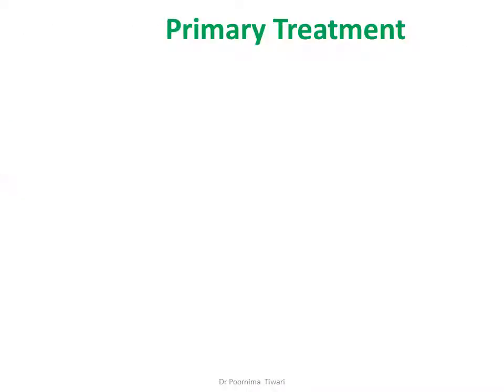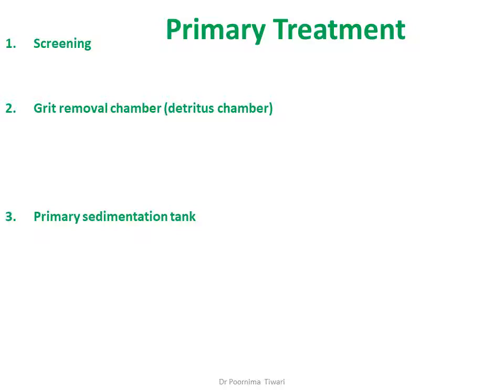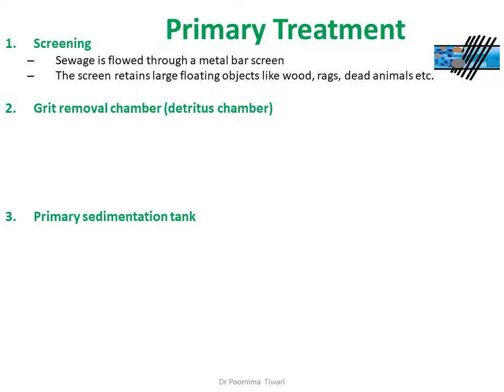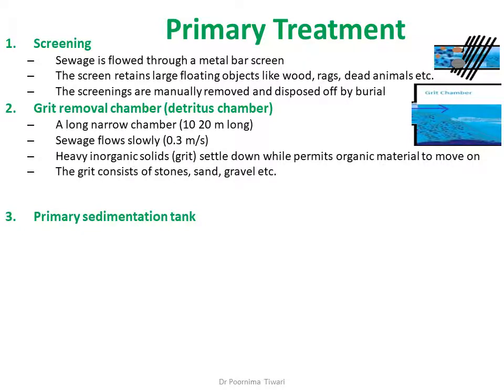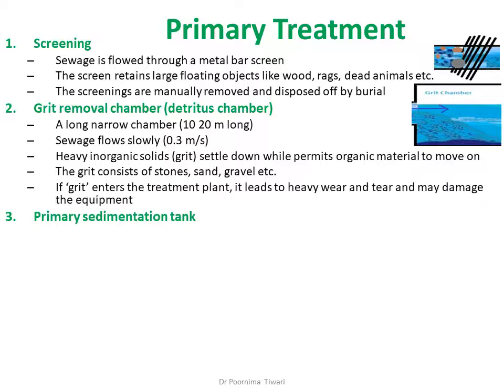Primary treatment in detail: the first step is screening, second is grit removal, and third is the primary sedimentation tank. In screening, sewage flows through a metal bar screen which retains large floating objects like wood, rags, and dead animals. The screenings are manually removed and disposed of by burial. The sewage then flows through a long narrow chamber known as the grit chamber, where it flows slowly enough to keep organic matter moving while heavy inorganic solids settle down. The grit — consisting of stones, sand, gravel — is removed to prevent wear and damage to plant equipment.